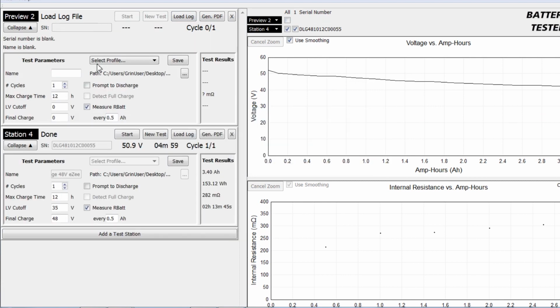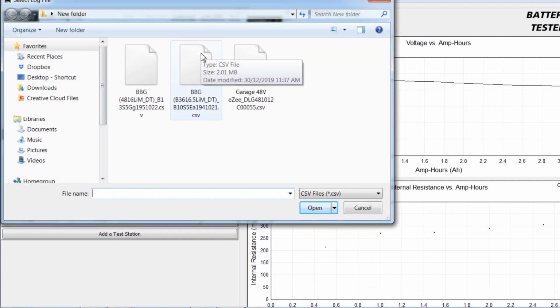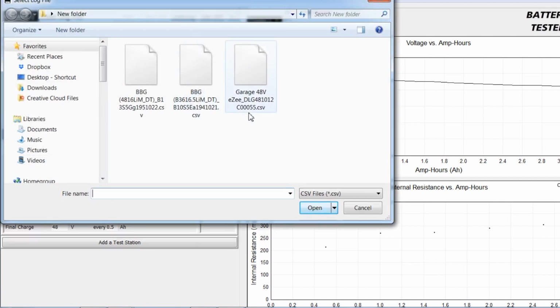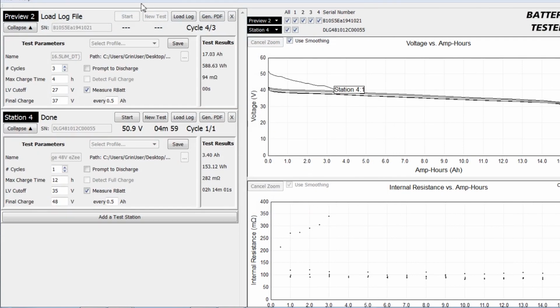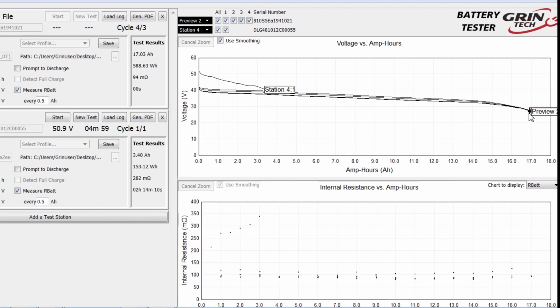This lets us open a pane for the Grinspector where we load a previous test file. Here, for example, I'll load a test file from a previous battery experiment, a 36 volt, 16.5 amp hour battery. Now we can restore all the data from that experiment, and you can see a more typical discharge curve, getting close to 17 amp hours from this 36 volt pack. You can see we actually did multiple discharges on this test.